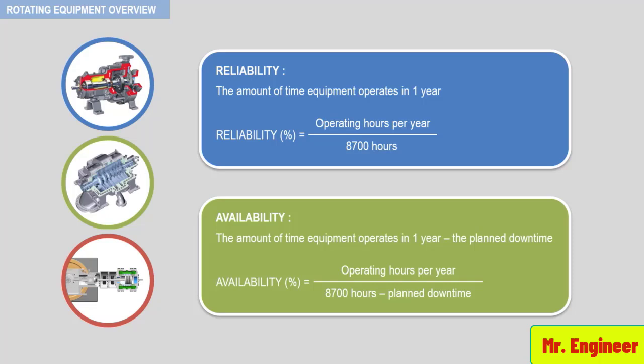Availability, on the other hand, considers planned downtime, including turnarounds. Both values are stated in percentage, and typical equipment availabilities when properly specified are 97% and above. Availability directly affects product revenue. For refineries, for example, the loss of revenue can exceed one million U.S. dollars a day if a critical piece of equipment is shut down.